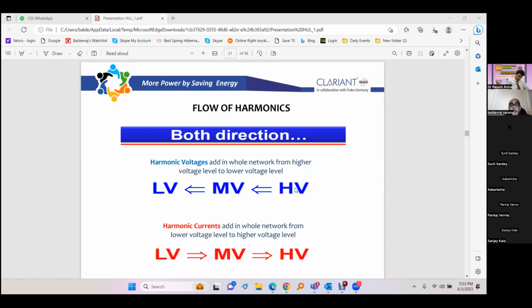It happens like that. So when we are not able to control current harmonics, there is big voltage distortion, big voltage harmonics in the grid, and that will affect everybody. And today the tariff structures are being made in such a way that consumers are responsible for maintaining current harmonics within limits. If they don't do it, they are penalized. And the voltage harmonics is the responsibility of the utility, the power supplier, to maintain.